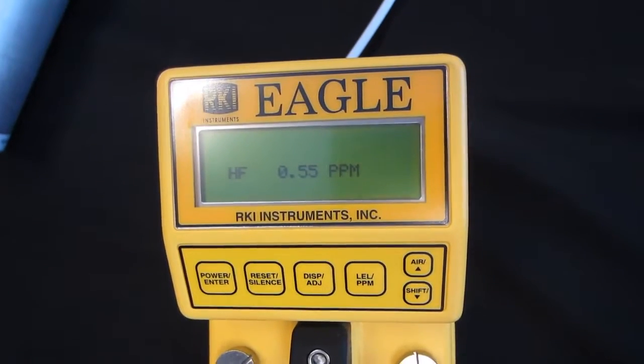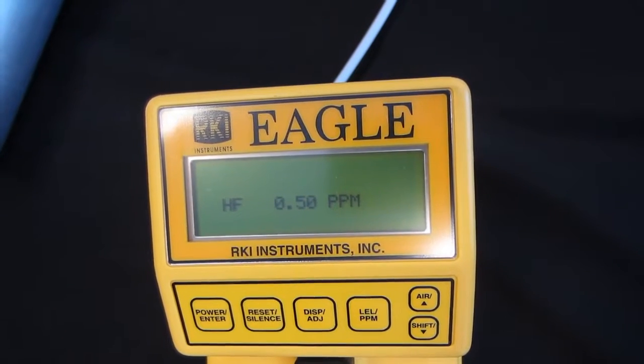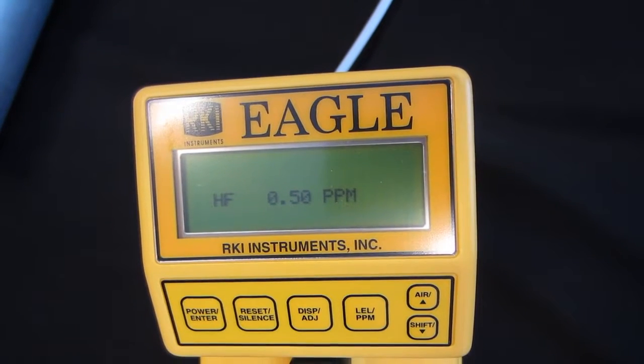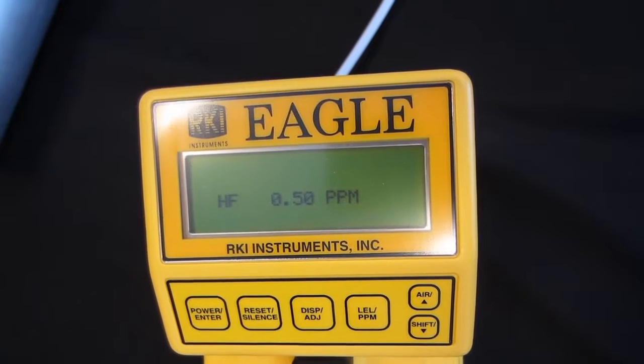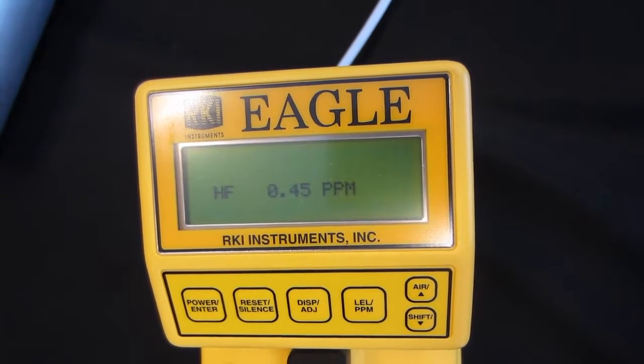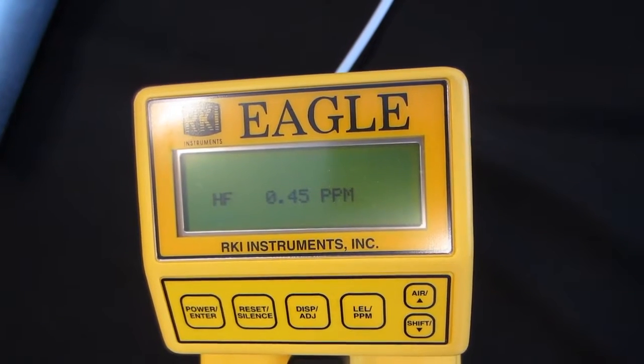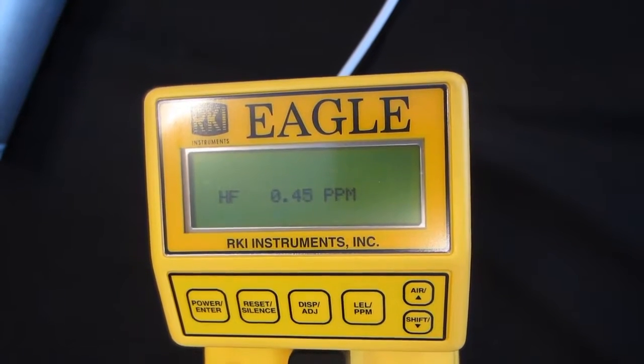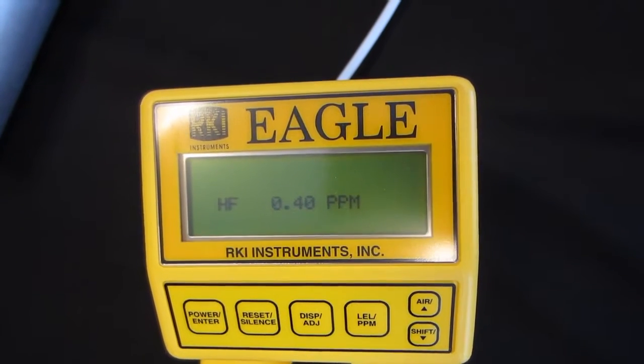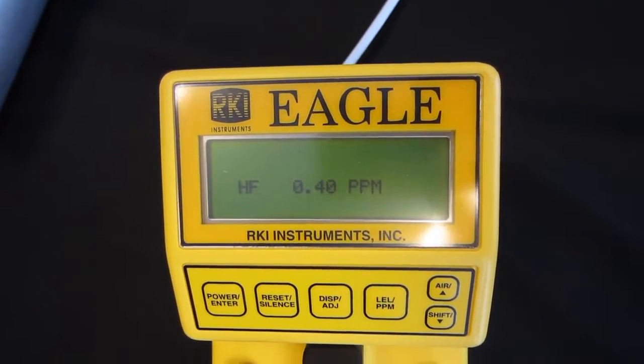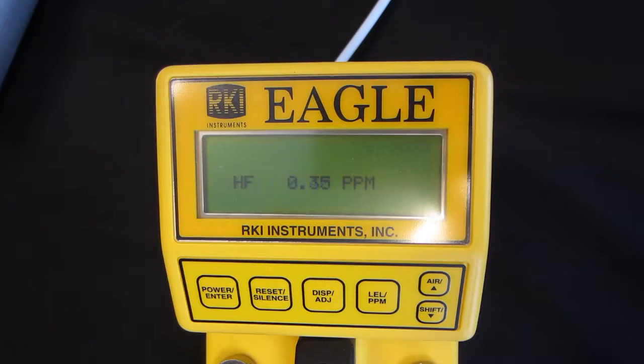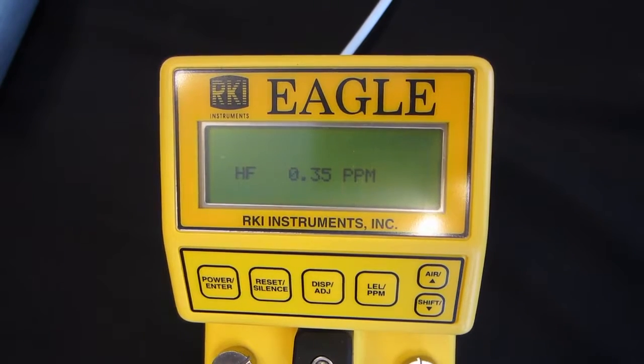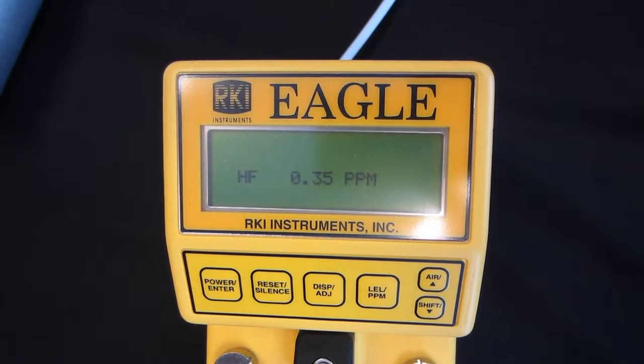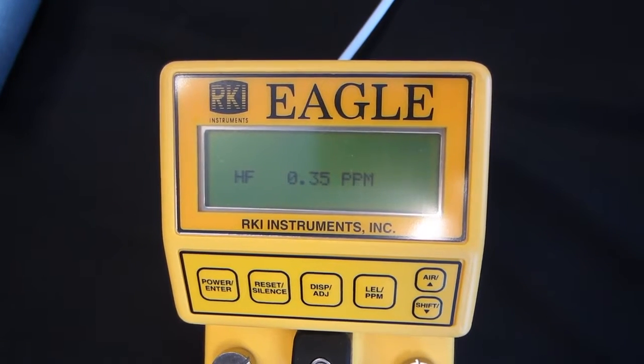And right now the reading will just continue to drop steadily until it gets to 0. Although you will note that very often when you get close to 0, but not quite, the unit can take several minutes before it finally clears out. So you want to give it plenty of time to clear out. If it hasn't cleared out after about 5 minutes, then go ahead and just press the air button, and that'll readjust everything back to 0 again.